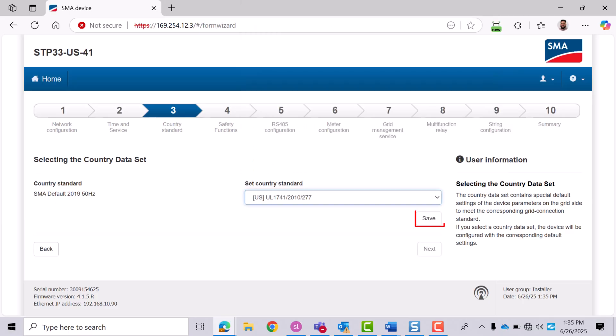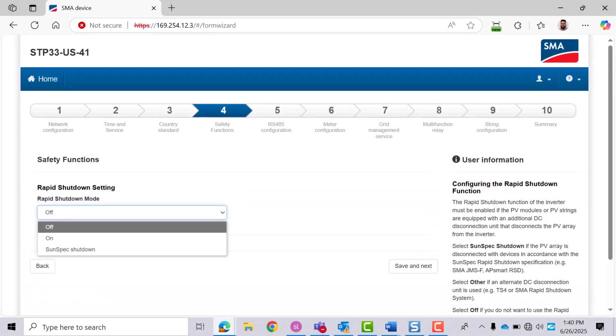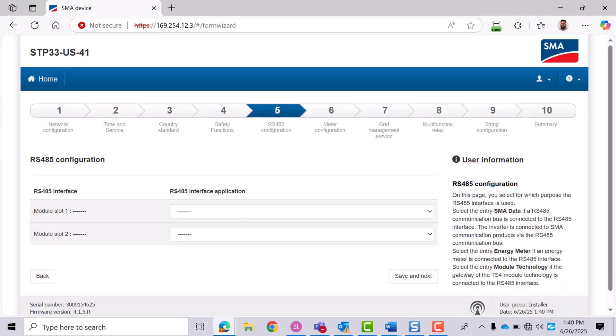Set up rapid shutdown settings. By default, rapid shutdown is deactivated. You can activate it after commissioning if required. Click Save and Next. This screen is for RS485 setup, but it's rarely used.